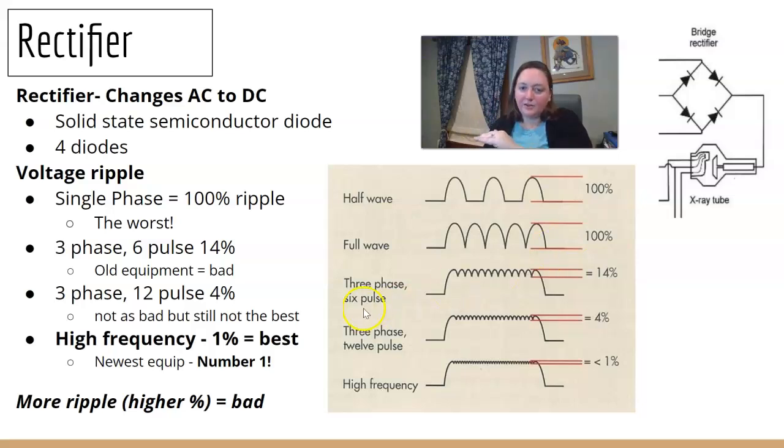The next equipment that we got, three phase, six pulse, fixed it a little bit. Because it added more pulses. So there was less drop. So now the ripple is only 14%. Three phase, 12. Again, we doubled those pulses to 12. It's only dropping 4%. And now your high frequency, it's dropping 1% or less. And so less ripple, the better. So I want you to remember, single phase is 100. High frequency is 1. We want the 1%. Because that's ideal.